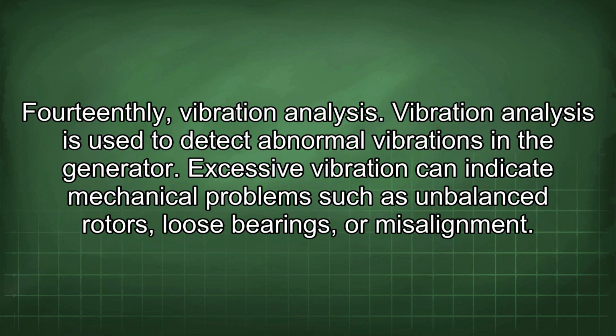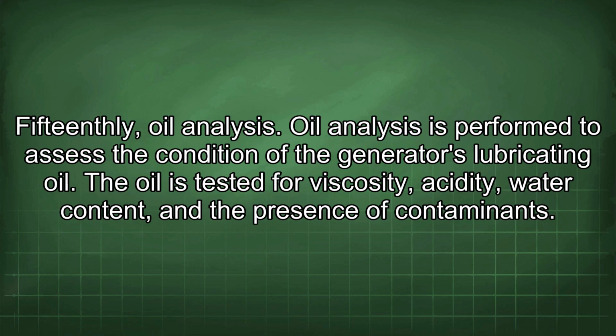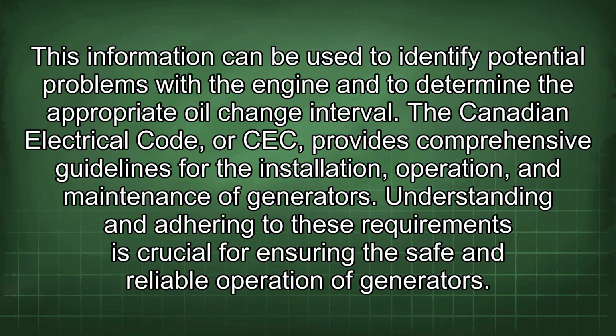14th, vibration analysis. Vibration analysis is used to detect abnormal vibrations in the generator. Excessive vibration can indicate mechanical problems such as unbalanced rotors, loose bearings, or misalignment. 15th, oil analysis. Oil analysis is performed to assess the condition of the generator's lubricating oil. The oil is tested for viscosity, acidity, water content, and the presence of contaminants. This information can be used to identify potential problems with the engine and to determine the appropriate oil change interval.